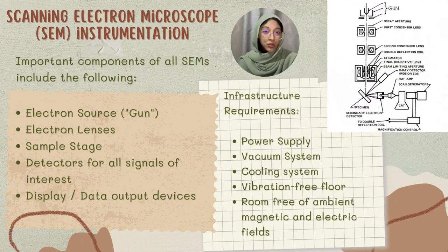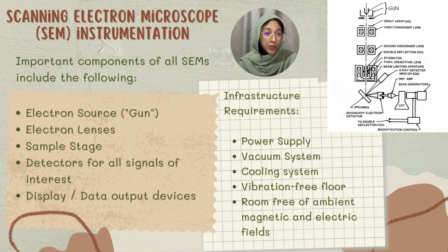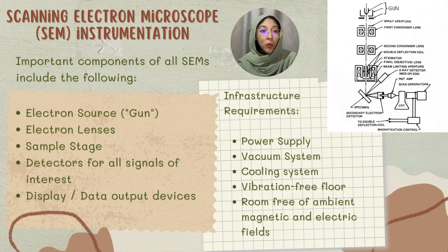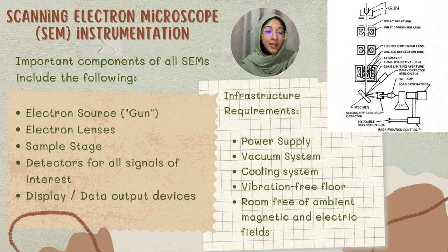The instrumentation of the scanning electron microscope includes the following important components: electron source (also known as gun), electron lenses, sample stage, detectors for all signals of interest, and display or data output devices. The infrastructure requirements include a power supply, vacuum system, cooling system, vibration-free floor, and a room free of ambient magnetic and electric fields.